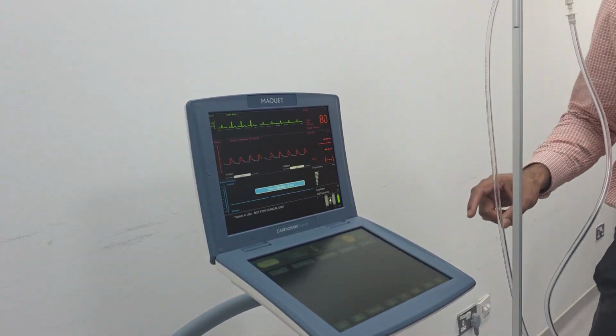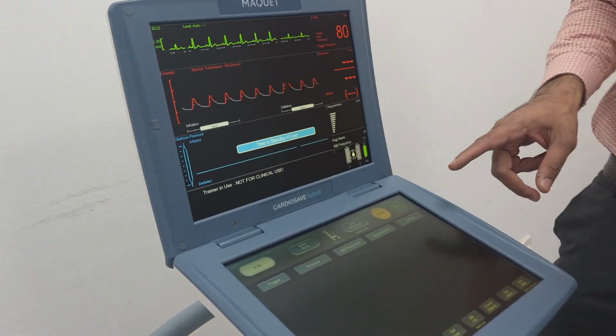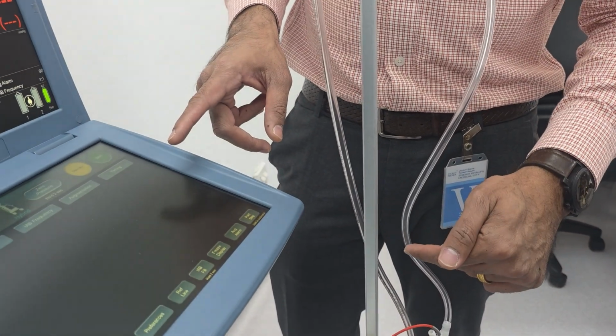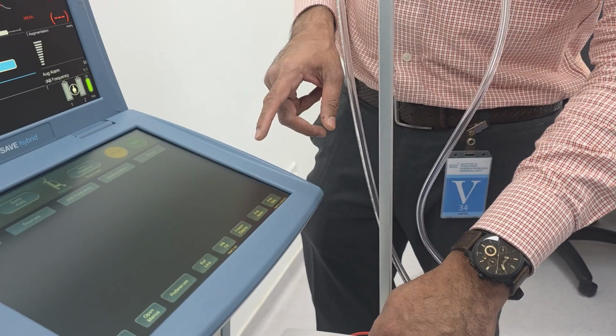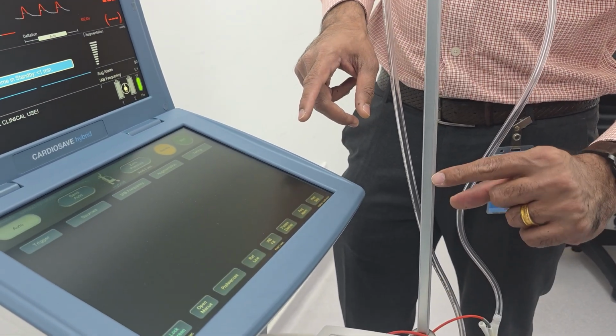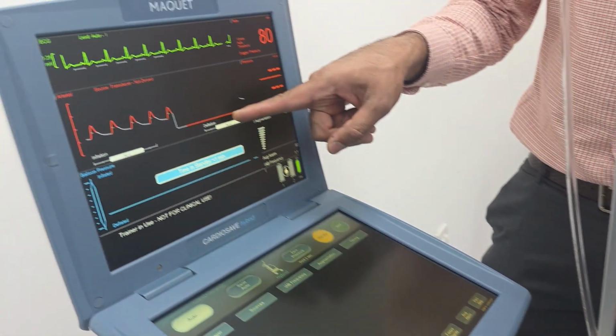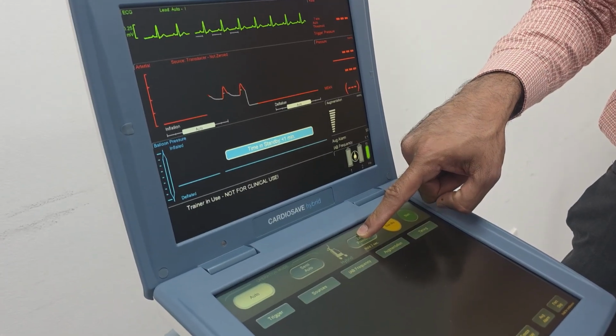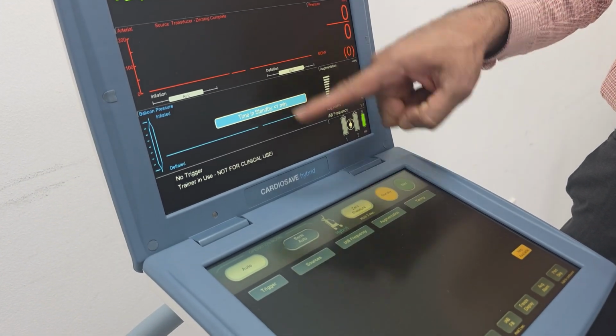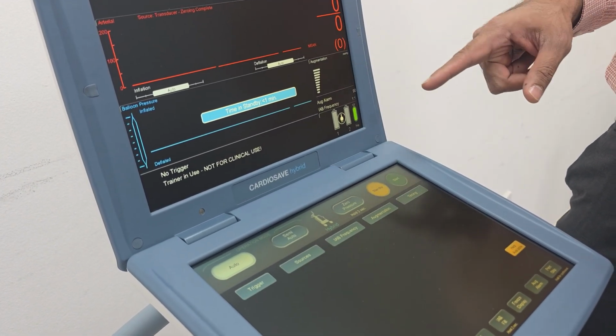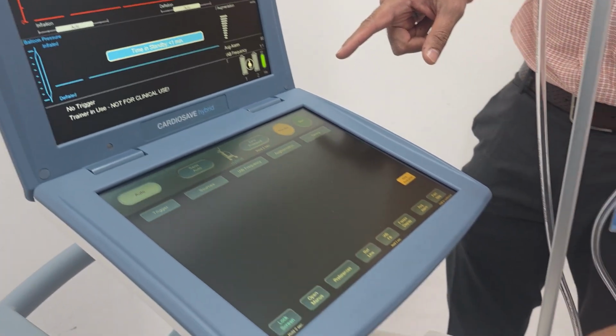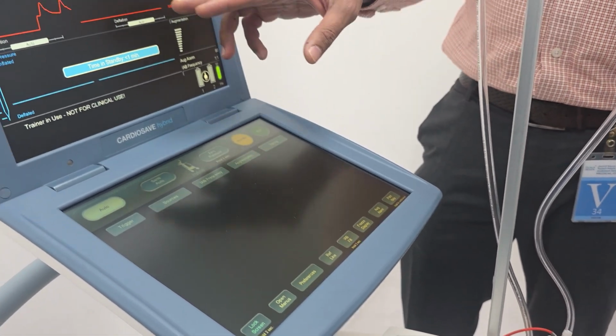So how to make 0? There are no values. You need to open the three-way stopcock to the atmosphere. Here I can do it in my simulator. Once you open to the atmosphere, there should be a straight line. Press and hold the 0 button for 2 seconds. Zeroing complete. You can see 0 values, and put it back to the line again. Here I will do it in my simulator. That's it. So we are getting values.